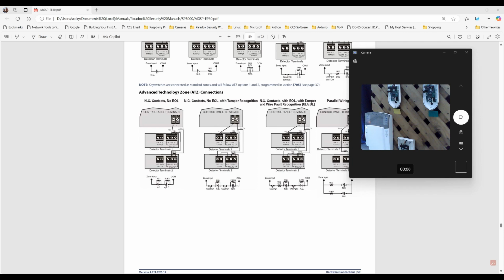So try to trigger them. You see this one was zone one. So now it's zone nine. This one was zone nine, now it became zone one. So if you choose to use zone doubling, you have to be careful how you wire your resistors, otherwise the zones will be mixed up and you might have a hard time troubleshooting. So you see, always 1K towards the zone. Now that we've done this, I'm going to put it back so we can continue our tutorial.